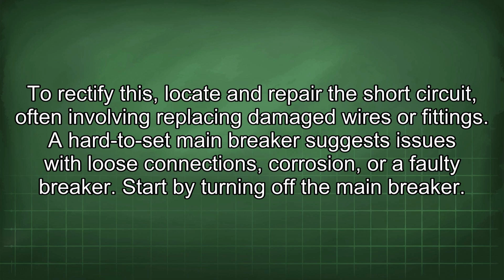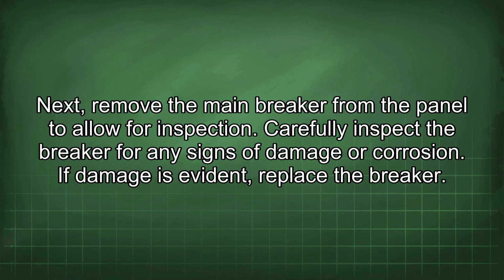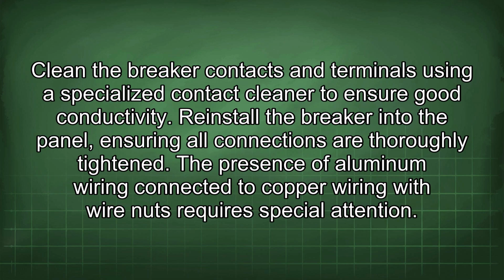A hard-to-set main breaker suggests issues with loose connections, corrosion, or a faulty breaker. Start by turning off the main breaker. Next, remove the main breaker from the panel to allow for inspection. Carefully inspect the breaker for any signs of damage or corrosion. If damage is evident, replace the breaker. Clean the breaker contacts and terminals using a specialized contact cleaner to ensure good conductivity. Reinstall the breaker into the panel, ensuring all connections are thoroughly tightened.